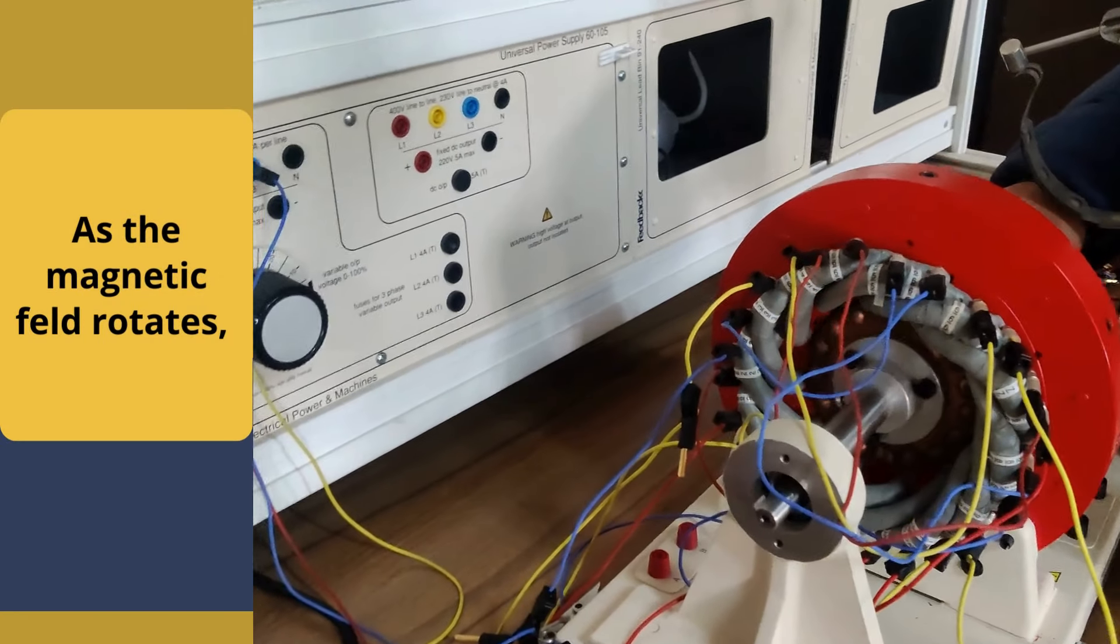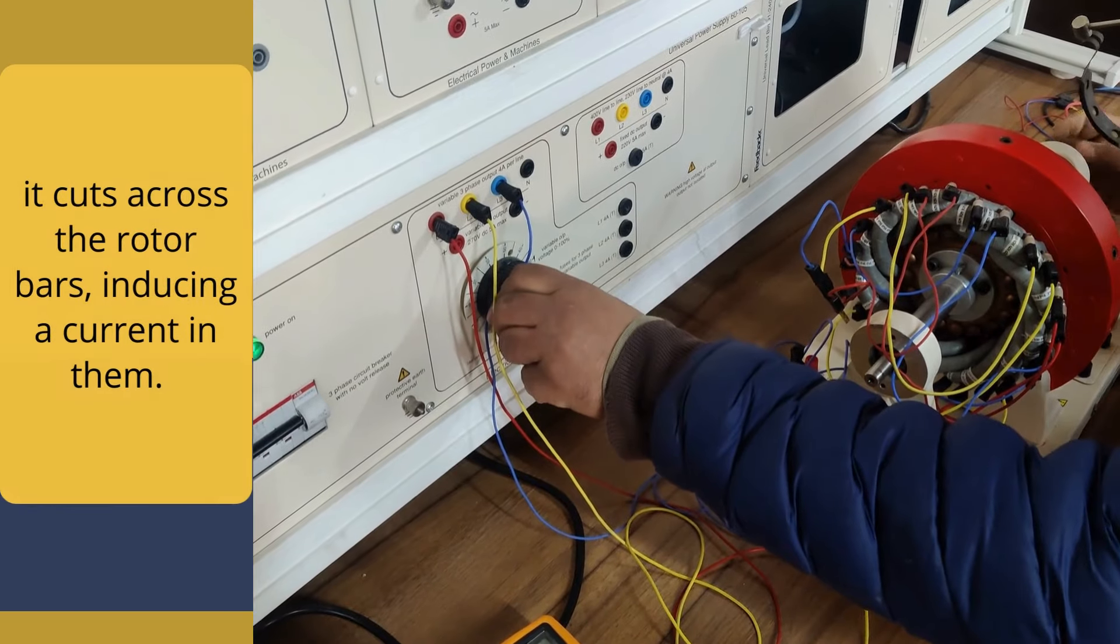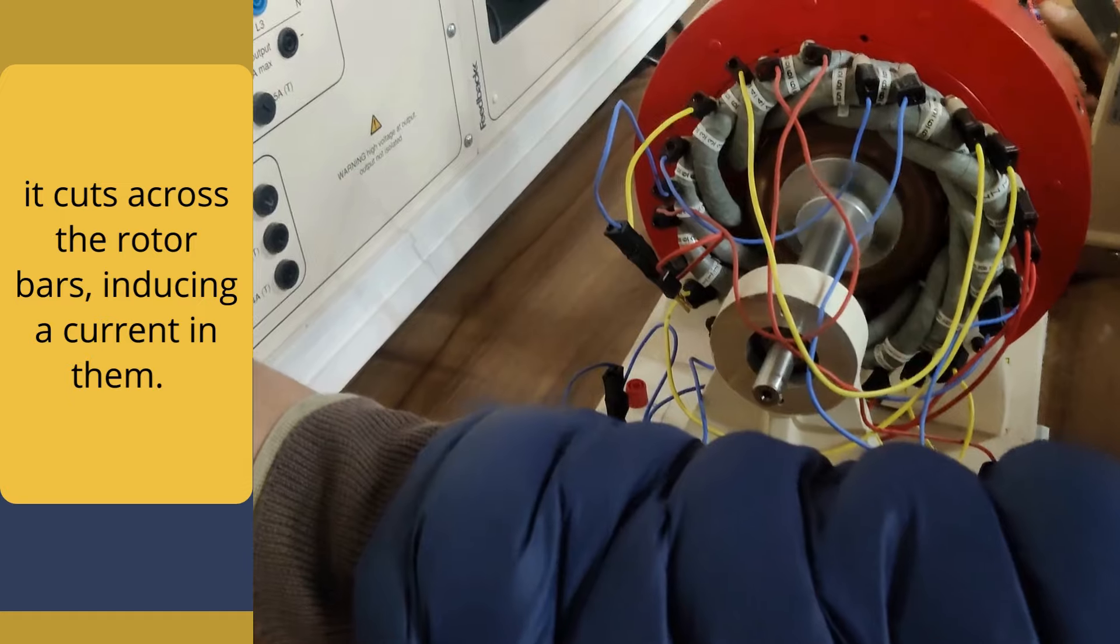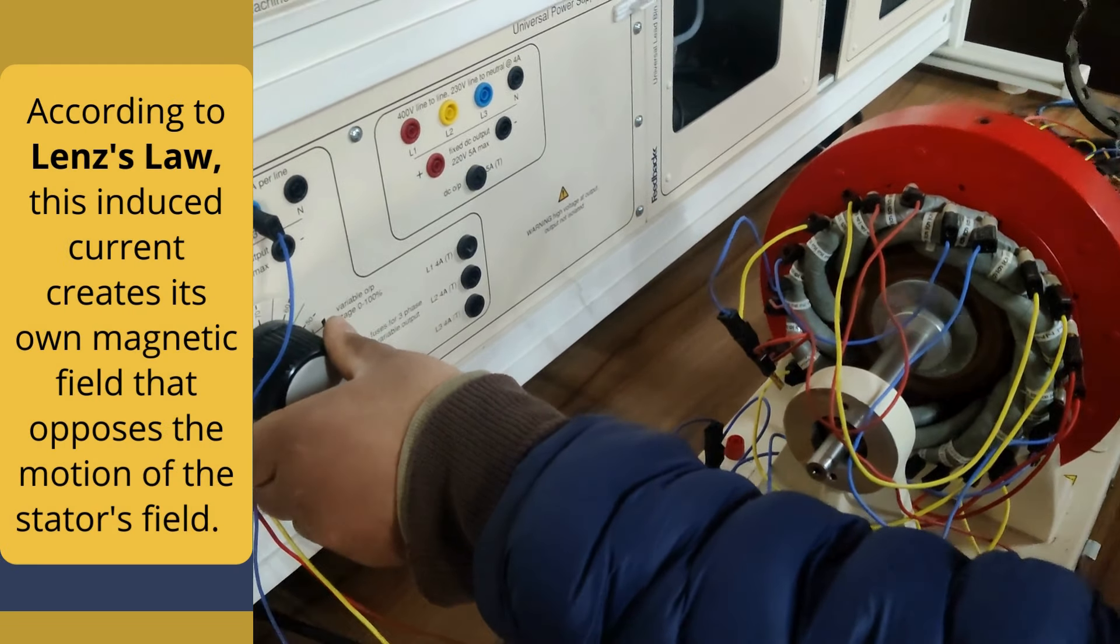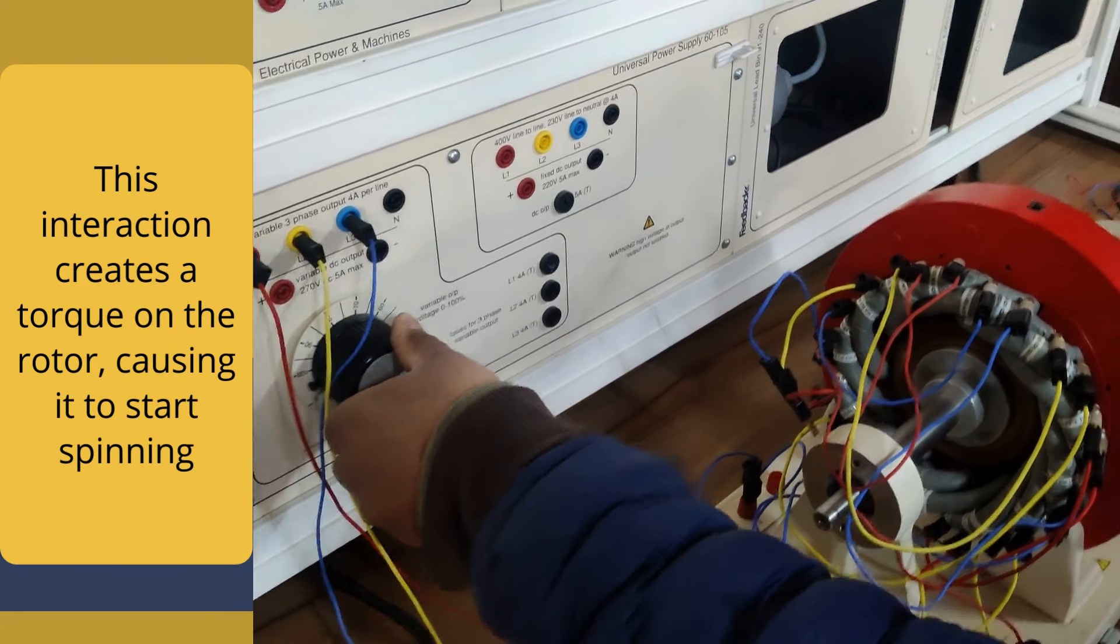Now you might wonder how the rotor actually starts turning. As the magnetic field rotates, it cuts across the rotor bars, inducing a current in them. According to Lenz's law, this induced current creates its own magnetic field that opposes the motion of the stator field. This interaction creates a torque on the rotor, causing it to start spinning.